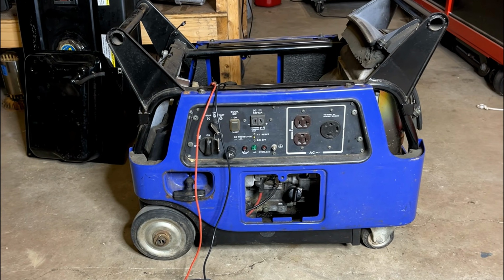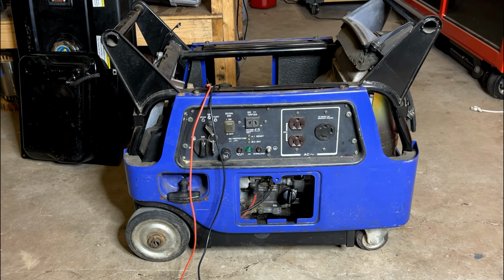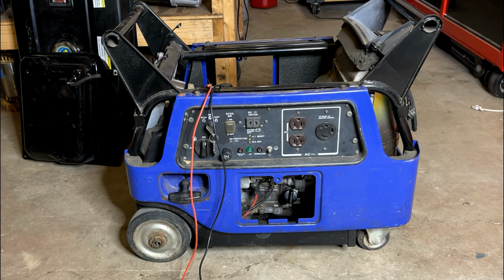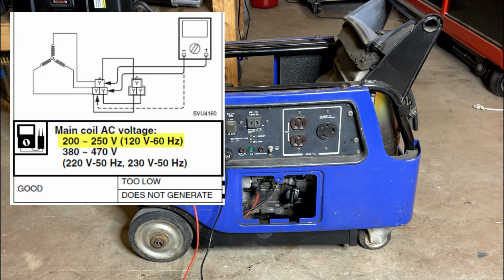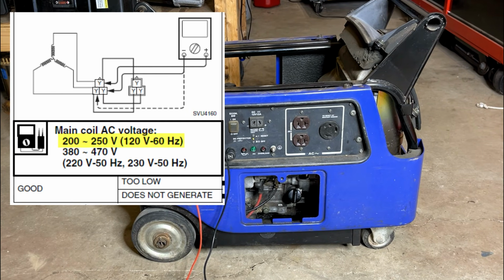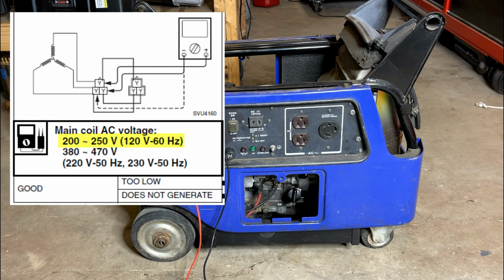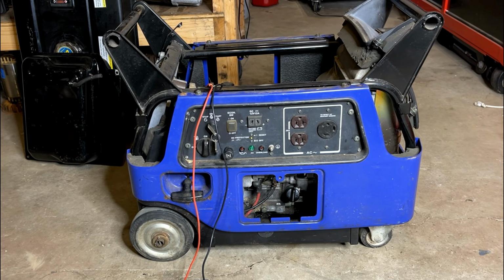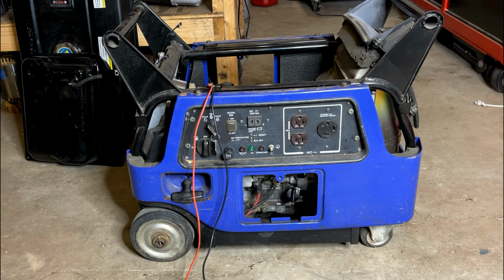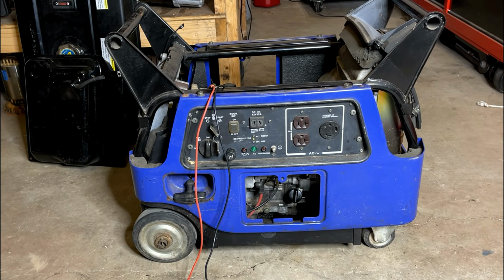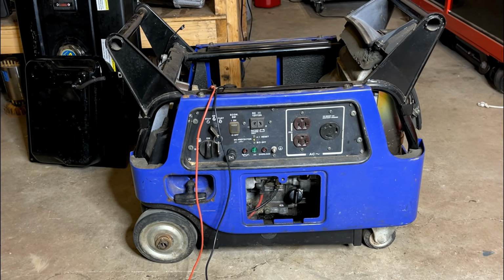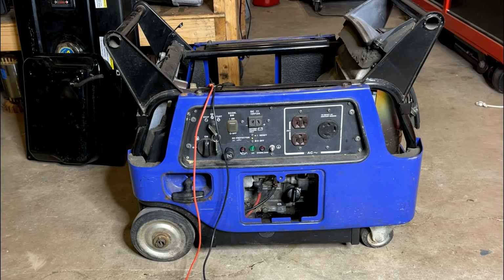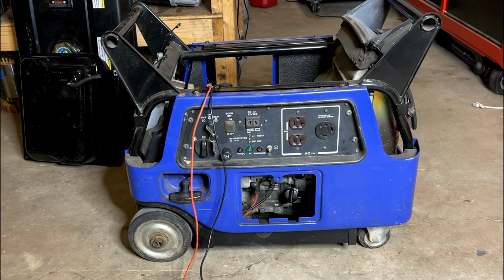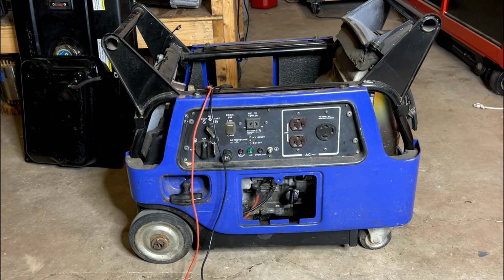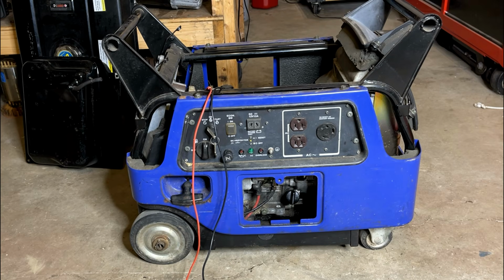The second piece of information was the expected voltage output on the 3-phase system at 3600 RPM. It gave a good range between 200 and 250 volts, which I got 220 volts on leg 1 and leg 2, but not leg 3 — I was almost 100 volts higher at 317 volts. So that had me concerned. That reading is out of spec.